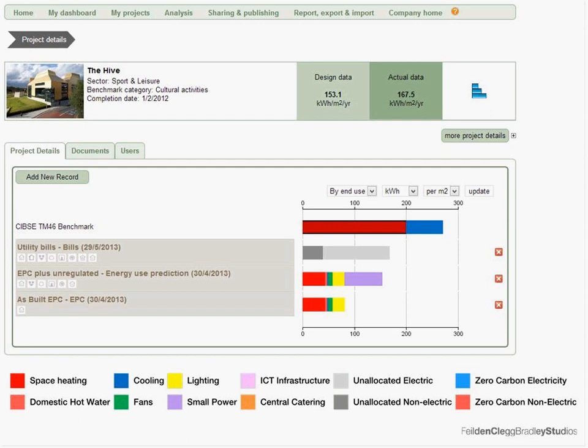But we can see actually, they do a pretty good job of guessing where use is going to be. If you look at the utility bills, there's not a huge gap between the two of them. Better than the first year of building occupation, so we expect there to be some settling in of building services and the control systems. The FM team get up to speed with how they're going to use the building, how the building is designed to be used, and what's the sort of mismatch.